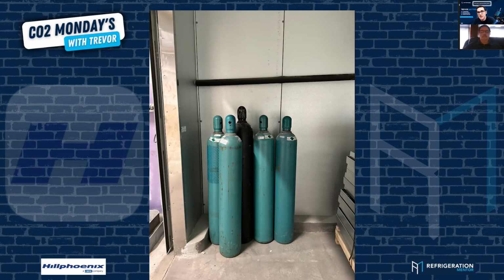Because there's another thing I seen in your manual where it says don't want to use Dewar tanks because they're lower pressure. You know what I mean? They're 300 inside and they're cool. But if you need refrigerant for your customer, and I know contractors use Dewar tanks on larger systems, that's what they start with, a bunch of Dewar tanks. You need to get your customer up and running. Yep. So it doesn't matter if it's Dewar tanks or if it's lower quality refrigerant.